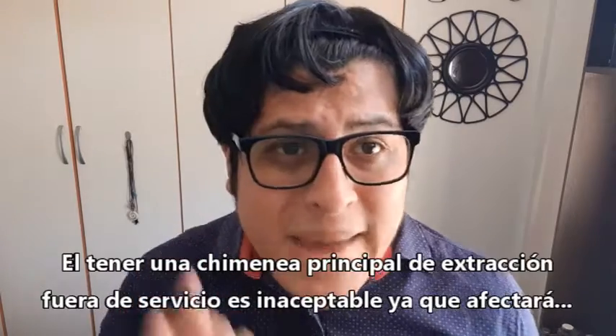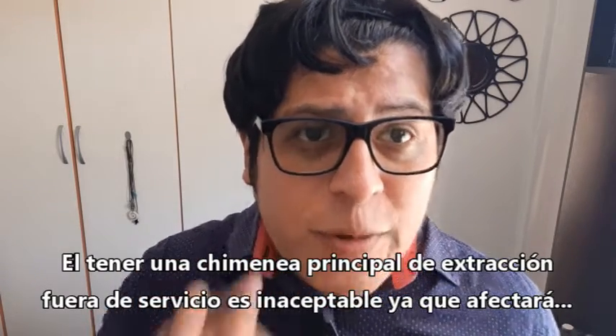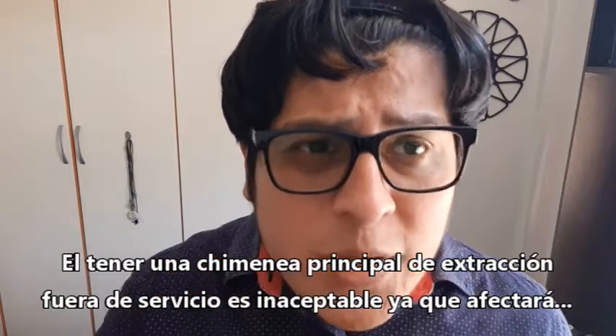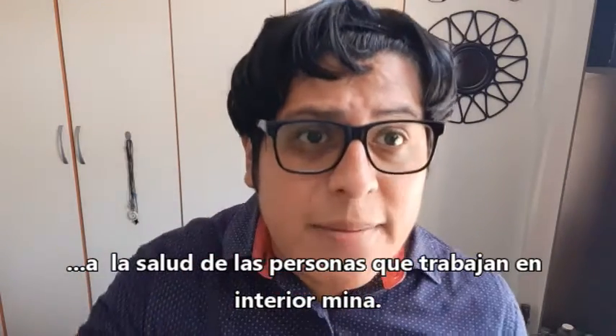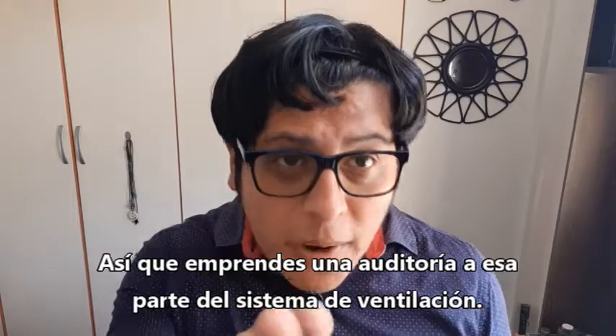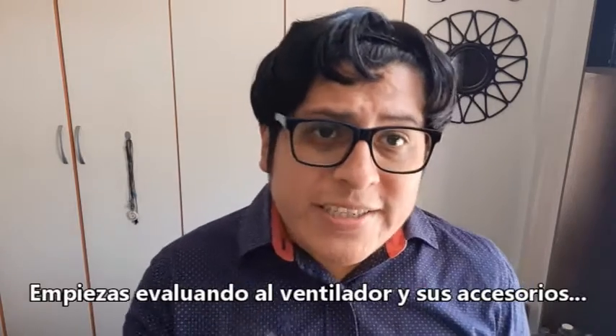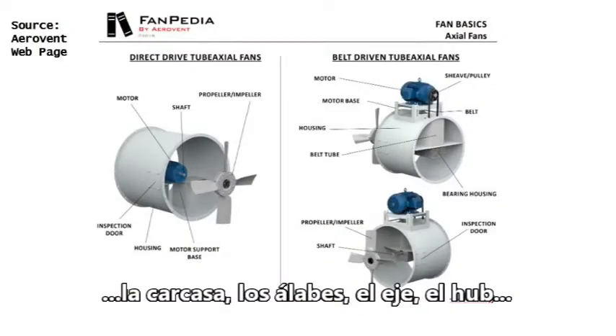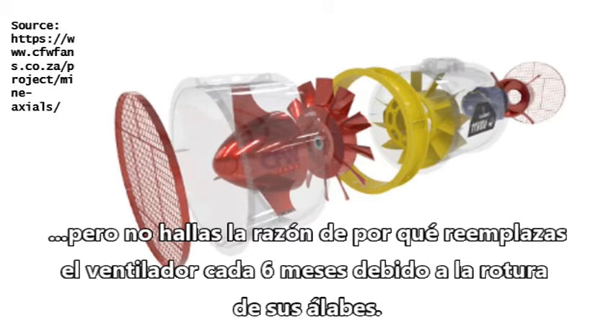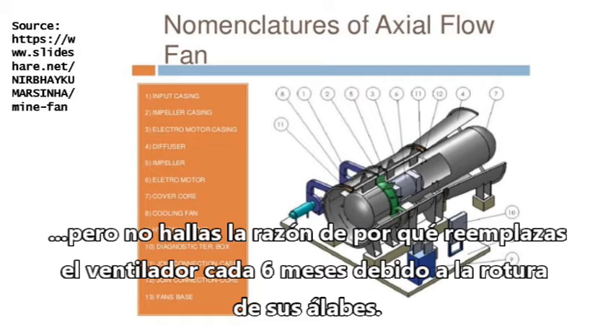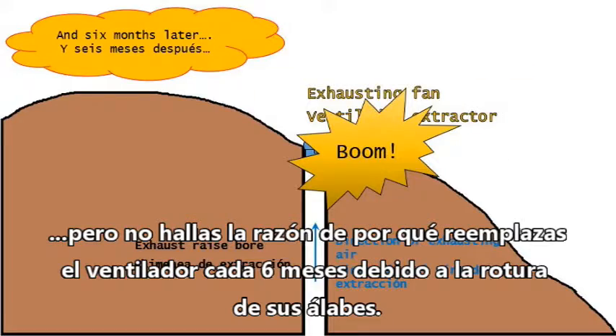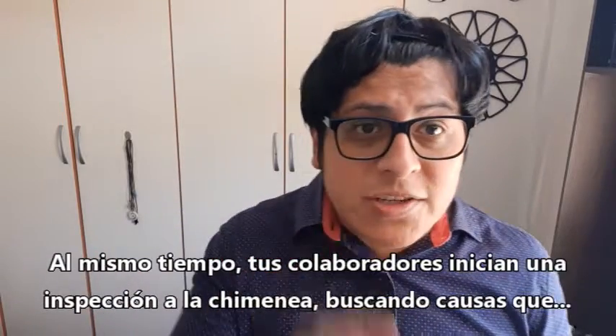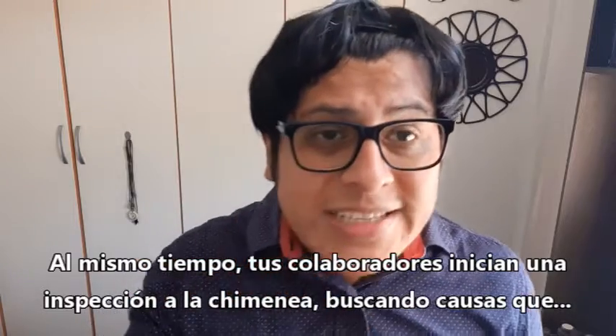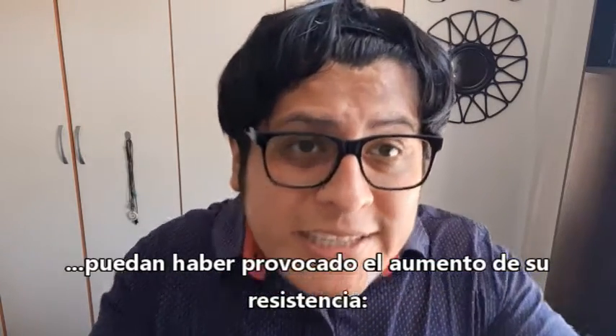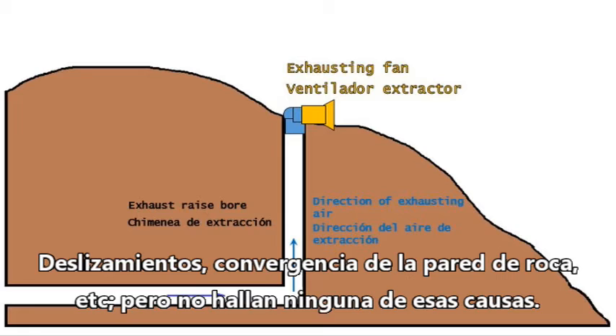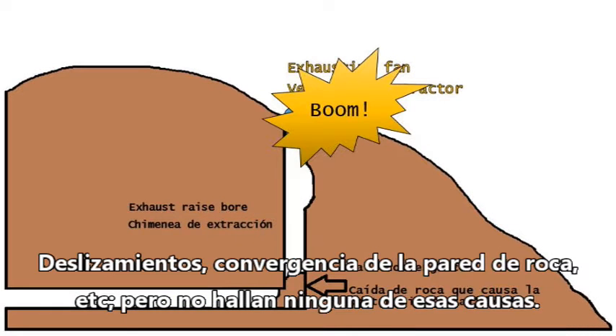Yes, I do. Having a main exhaust raise out of service so frequently is unacceptable from the point of view of the well-being of the people inside the mine. So you do some auditing of that part of your mine ventilation system. You start assessing the fan installation, casing, blades, shaft, hub, but find nothing that could be directly involved in why every 6 months you have to repair the fan because its blades went off. At the same time, part of your personnel start inspecting the raise looking for causes that may have increased its resistance. Sloughing, wall convergence, etc. But again, nothing wrong is found.